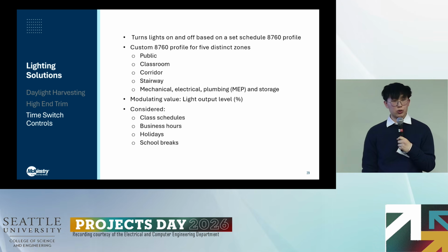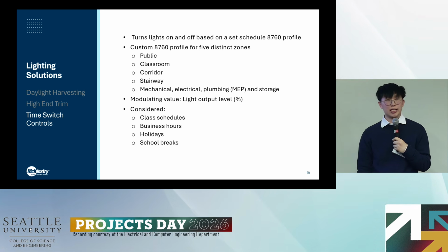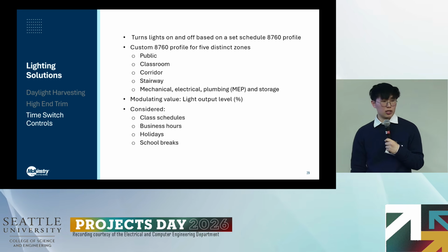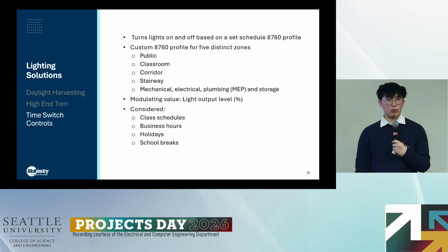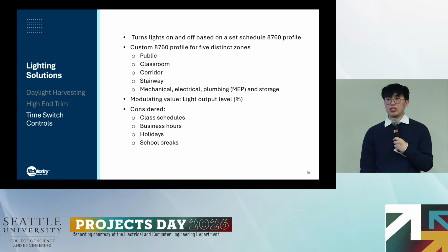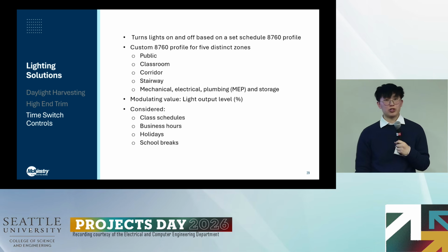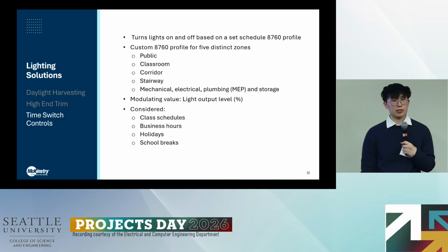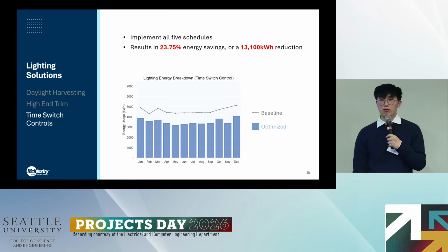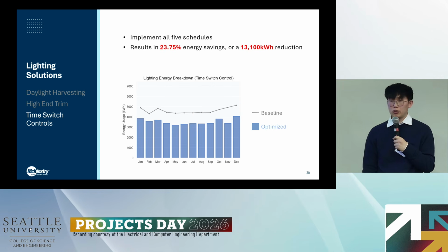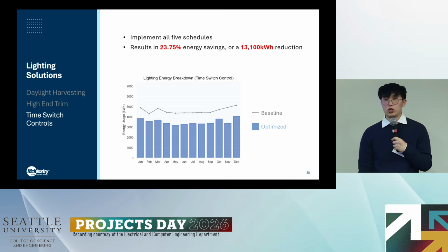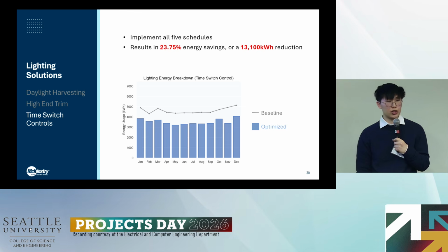Our last lighting control strategy is time switch controls, which turns the lights on and off based off of a custom 8760 schedule. We created 5 distinct schedules for 5 distinct zones, and for each of these schedules, we changed the modulating value, which was the light output as a percentage. And while creating these schedules, we took into consideration class schedules, business hours, holidays, and school breaks. So implementing all 5 of these schedules, we get the monthly total output as a graph. And this resulted in about a 24% energy savings, or 13,100 kilowatt hour reduction from the lighting baseline.